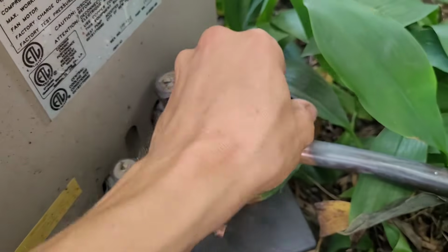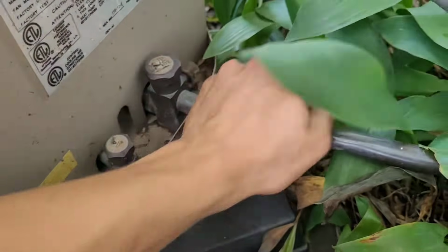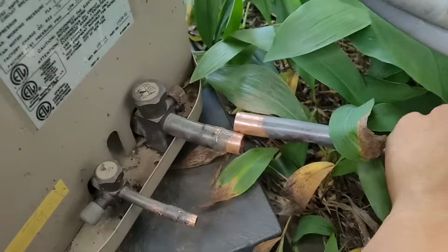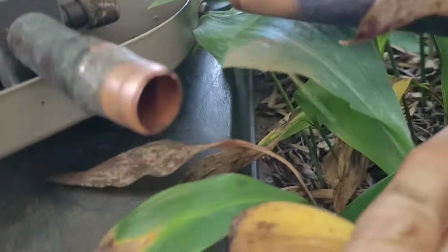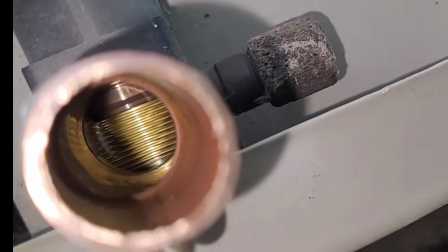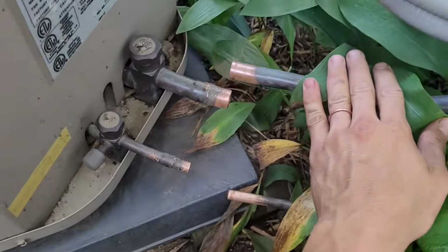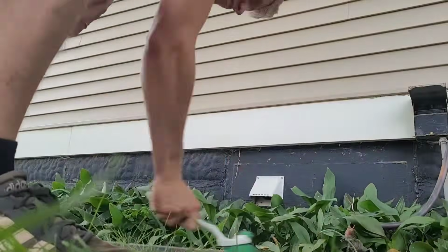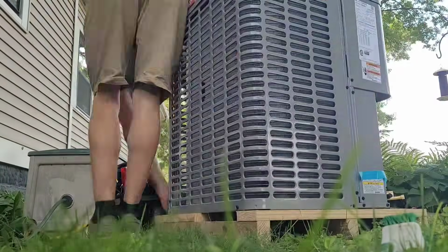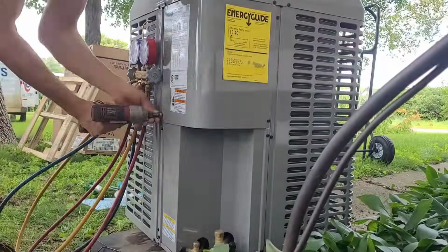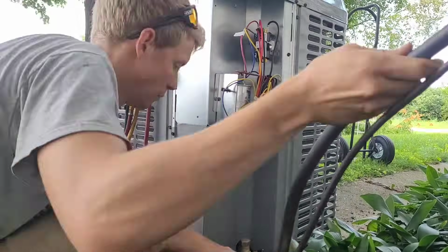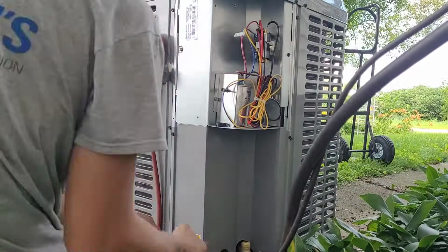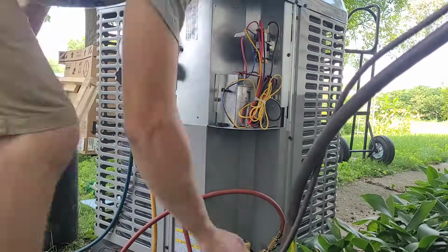Just cutting the line set off here. Didn't have to recover any refrigerant, obviously, since it had blown. Clean in there. Standard air conditioner really doesn't have that much hooked up to it. You've got the large suction line, the small liquid line, 2 wires for the low voltage and 2 wires for the high voltage. Some people get kind of whiny when I call anything high voltage that's less than like 10,000 volts. Obviously, high voltage in this case is relative to our low voltage control circuit.